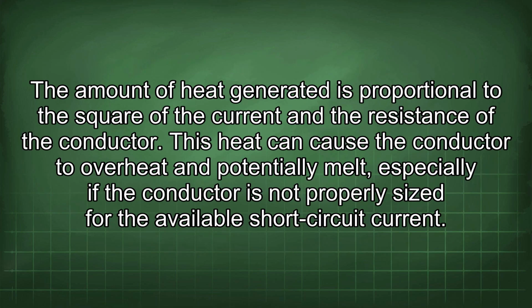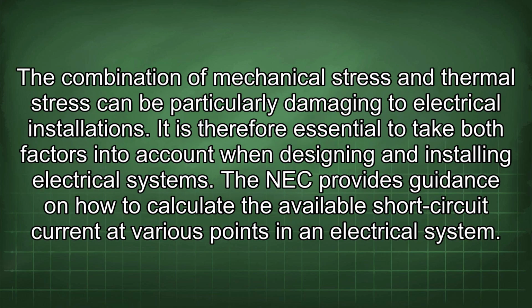The amount of heat generated is proportional to the square of the current and the resistance of the conductor. This heat can cause the conductor to overheat and potentially melt, especially if the conductor is not properly sized for the available short-circuit current. The combination of mechanical stress and thermal stress can be particularly damaging to electrical installations. It is therefore essential to take both factors into account when designing and installing electrical systems.